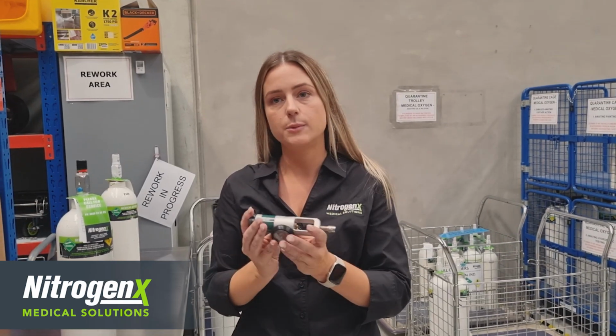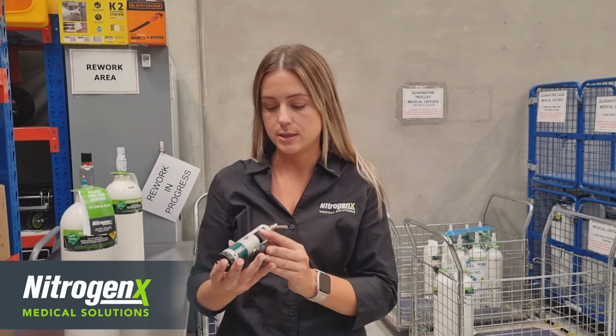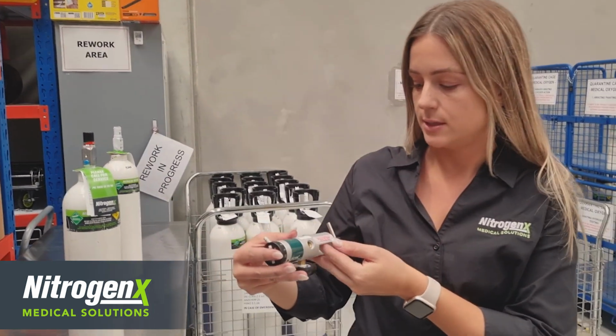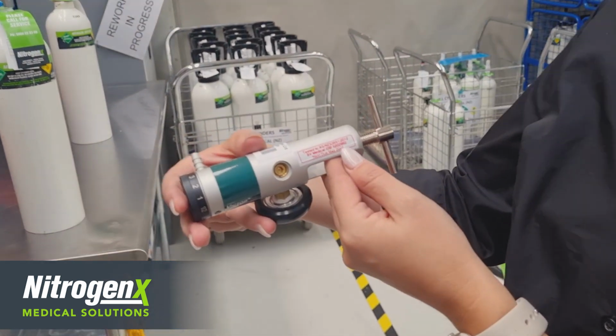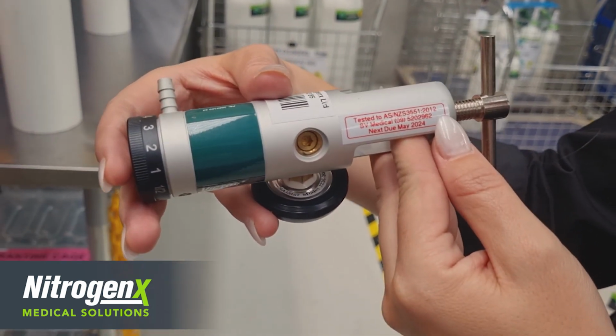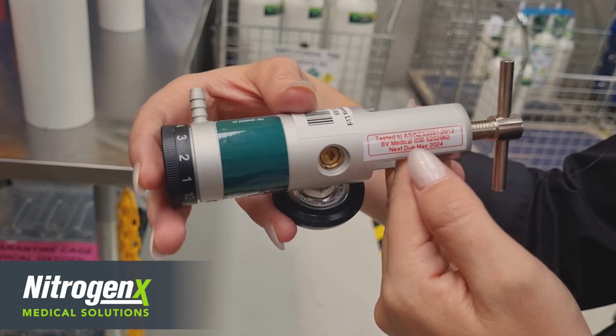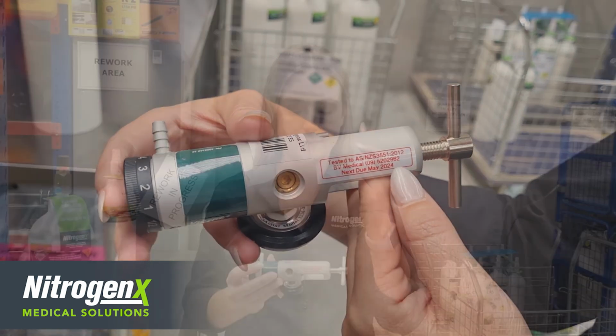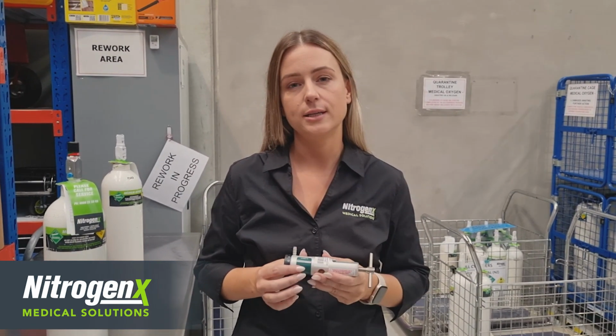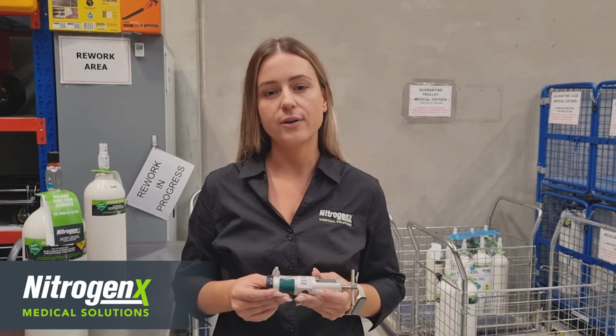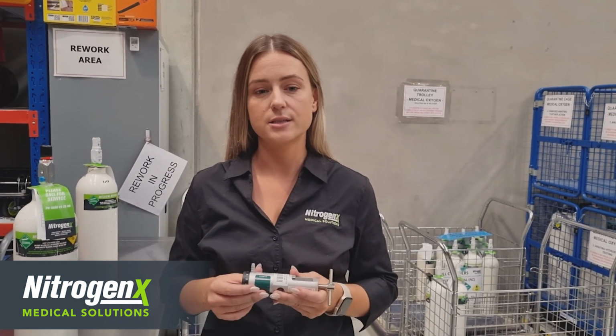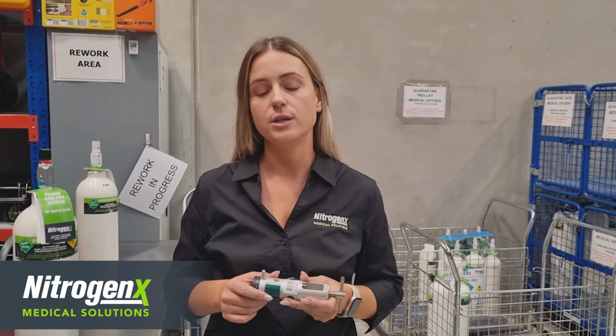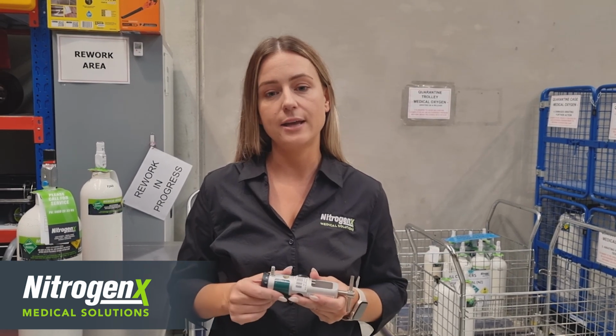Each regulator needs to be calibrated every 12 months. An easy way to identify this is with the sticker that should be on the side of it. It'll tell you when it was last tested, who tested it, and when it's next due for calibration. Every medical device in New Zealand needs to be annually performance verified to meet the New Zealand standards. This includes medical oxygen regulators, which need to be verified annually for the duration of their life.